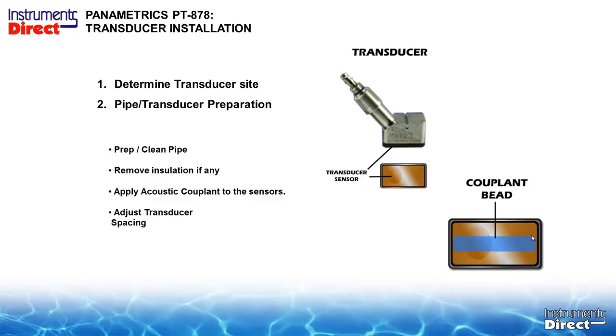Sound travels faster through a solid, hence the acoustic couplant is the solid that transfers the sound through. You need to prep your pipe, so if you have insulation on the pipe, you cut a complete horizontal cut and remove the insulation off the outside of the pipe.